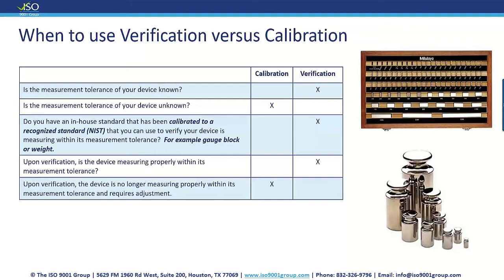Another thing to think about. Do you have an in-house standard that has been calibrated to a recognized standard? In the ISO and other standards, it always refers us back to NIST, that you can use to verify your device is measuring within its measurement tolerance. For example, it could be a gauge block or weight. We have some examples over here of some gauge blocks. Now, these gauge blocks would need to be calibrated by an outside source. Then you could use these blocks to verify your device. Or these weights here, you could easily put onto your scales because these weights would be calibrated, and then you could verify your scale using these calibrated standards.